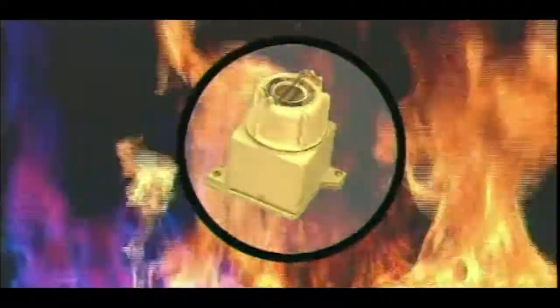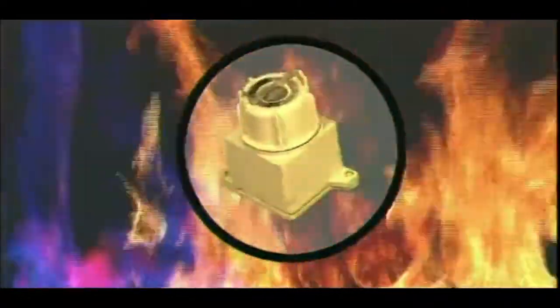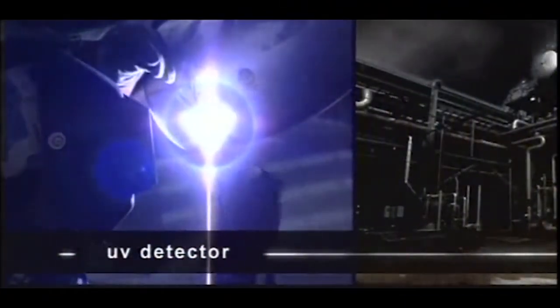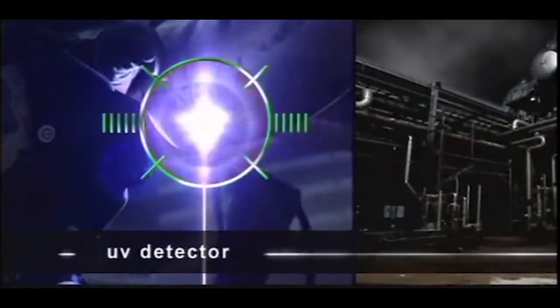Detecting fire may be more difficult than you think. Optical flame detectors have long suffered from limitations inherent in their design or the technology they use. This means that a fire can go undetected, or that the detector frequently alarms when a fire is not present. For example, ultraviolet detectors will false alarm when lightning or electric arc welding is present.